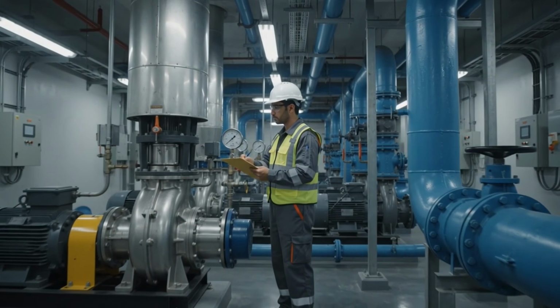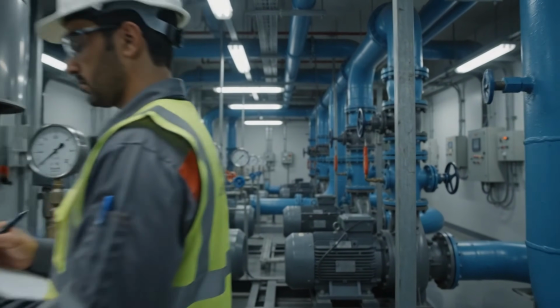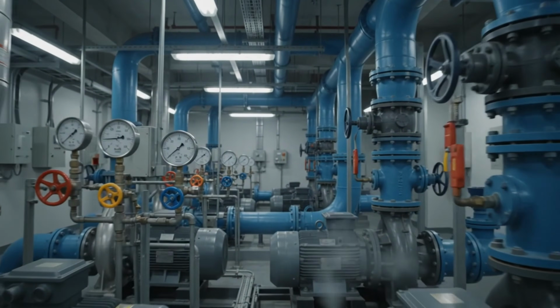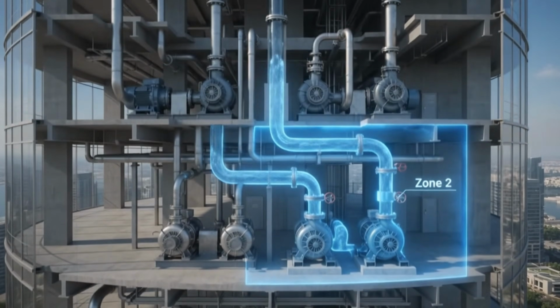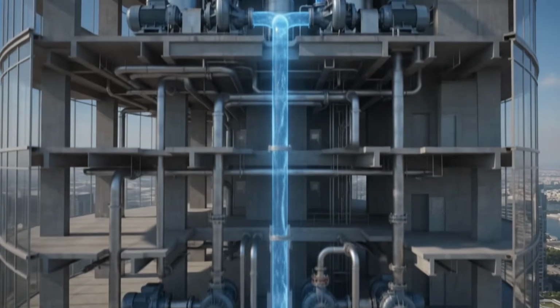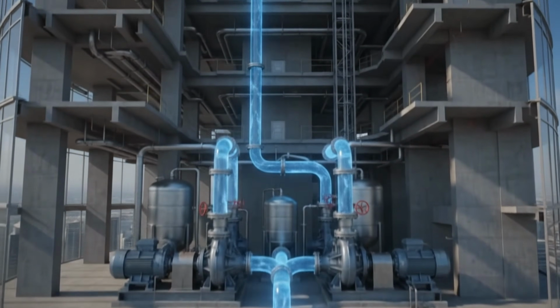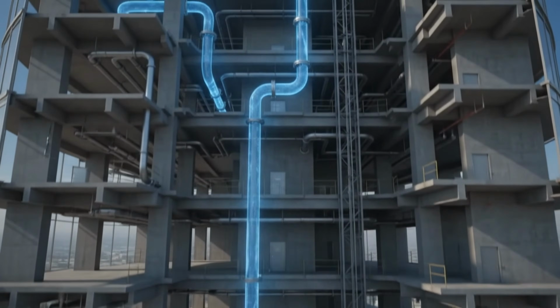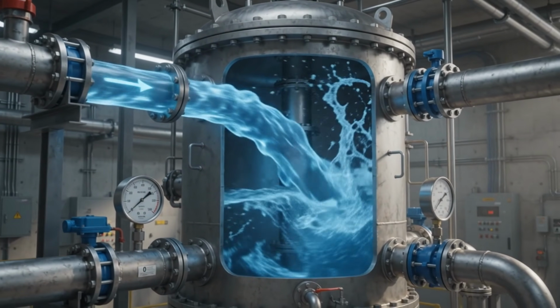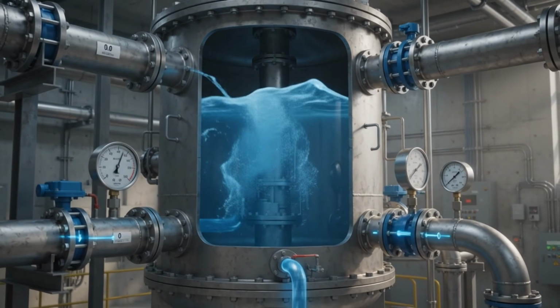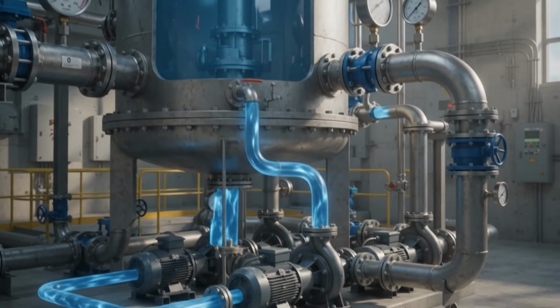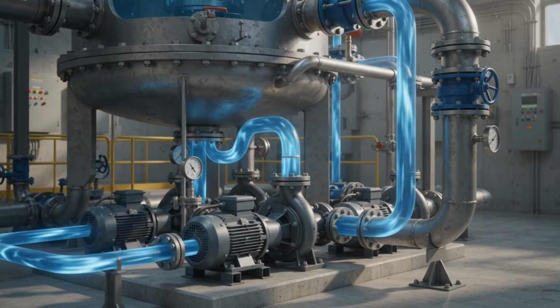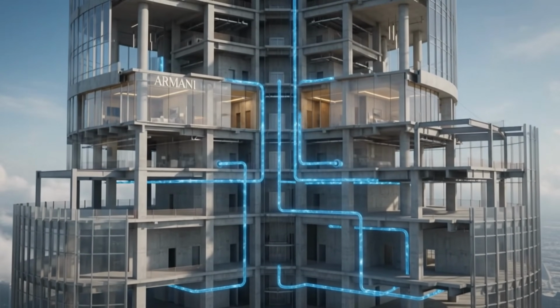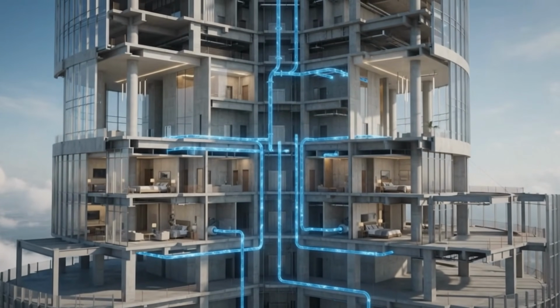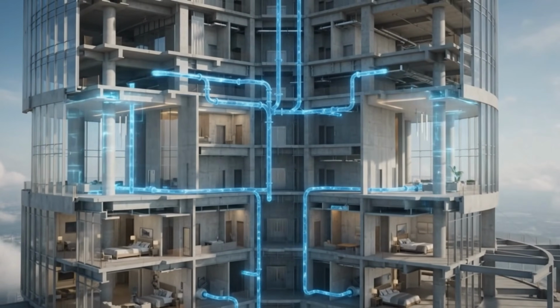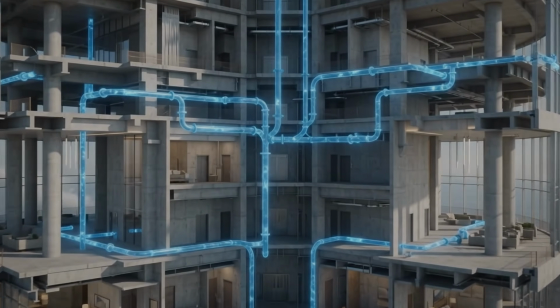Engineers conduct daily inspections, testing valve responses, verifying that every component is performing within operational limits. At floor 45, Zone 2 takes over. A new set of pumps receives water from the Zone 1 upper storage tank and begins the next stage of the upward relay. The handoff between zones is a carefully timed engineering sequence. Water fills the relay tank, pressure resets to 0, and the next pump set takes over with a clean pressure baseline. Zone 2 spans the tower's midsection, home to the Armani Hotel's upper floors, private residences, and the sky-high observation lobbies that draw millions of visitors annually.